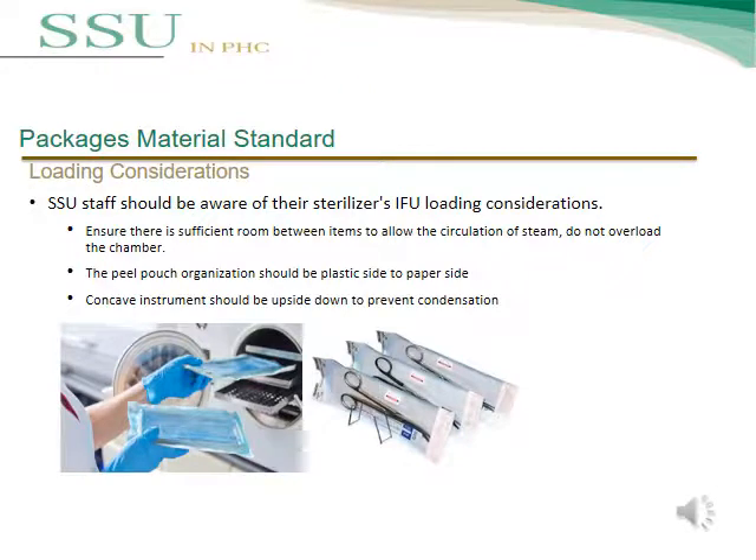Loading consideration is an important topic. SSU staff should be aware of their sterilizer IFU loading considerations. Ensure there is sufficient room between items to allow circulation of steam, and do not overload the chamber. The peel pouch orientation should be plastic side to paper side. Concave instruments should be placed upside down to prevent condensation.